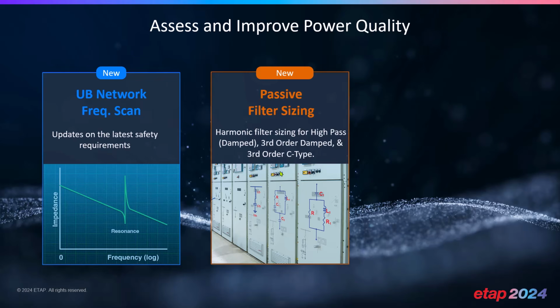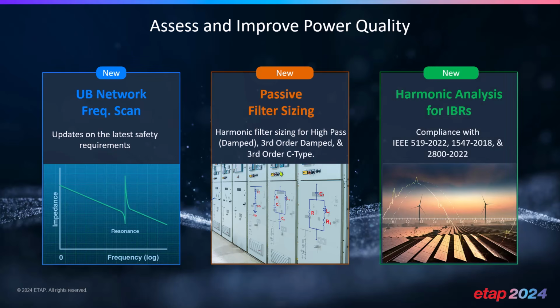And of course, with, again, proliferation of energy storage devices and renewable energy, comes the core component, which is inverters or inverter-based resources. And of course, there have been latest changes in the harmonic standards, particularly in IEEE 519. So ETAP 2024, of course, includes compliance and rules based on IEEE 519 2022, based on IEEE 1547, as well as IEEE 2800, in order to make sure that you are up to date with the latest standards that are needed for power quality compliance.